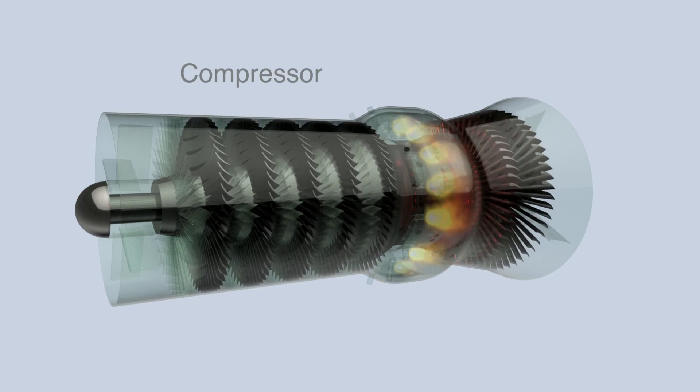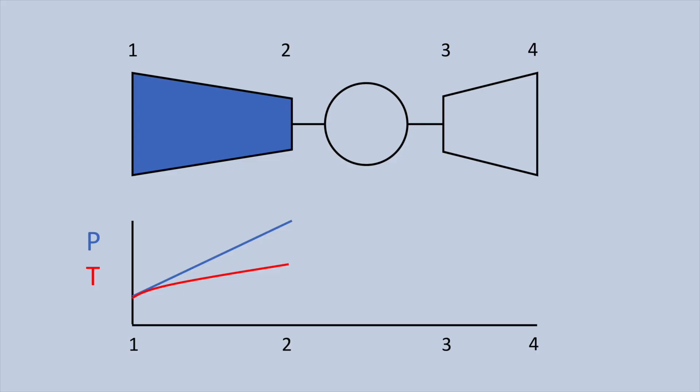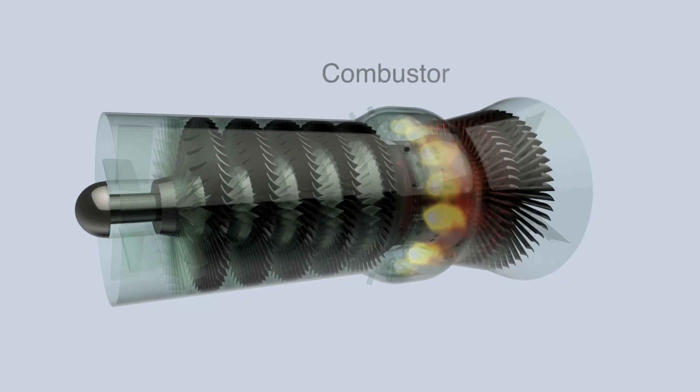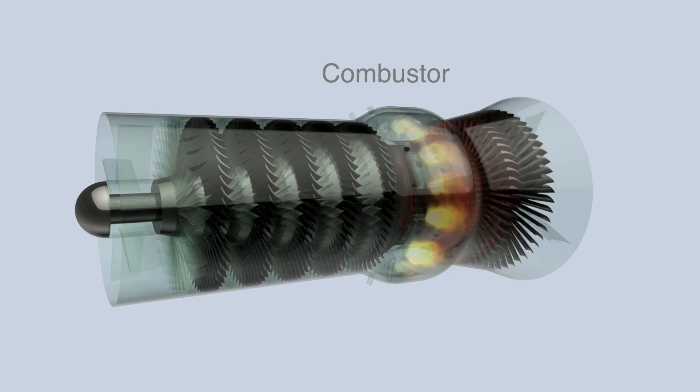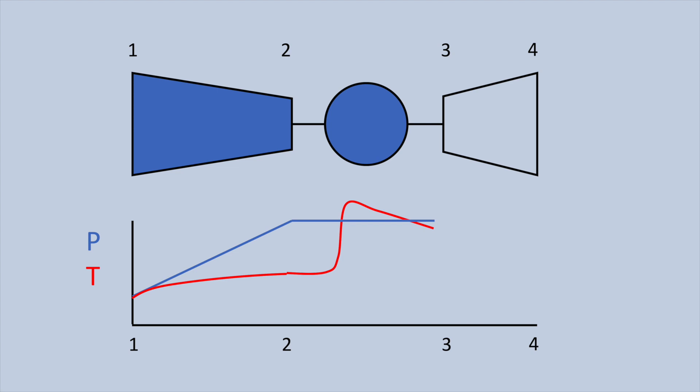Air enters the engine on the left and passes first through the compressor where the pressure and temperature are increased. Air then enters the combustor where fuel is added and ignited in a self-sustaining continuous flame. This causes the temperature to rise. A fraction of the air bypasses the flame to cool the combustor and inlet of the turbine, and this air causes the temperature to drop slightly after the flame.